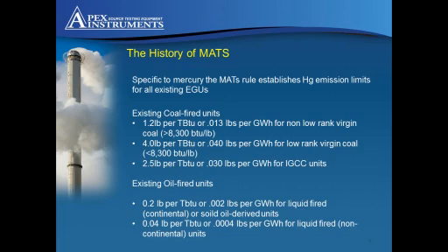It is still unclear if, by reporting emissions against one of these values, you are then locked in to that reporting specification or you can change at will. We are yet to get a determination from the EPA on this particular question. Again, I would like to reiterate that these values on the screen currently are limits for existing EGUs, defined as anything built or reconstructed before the 3rd of May 2011. These limits also apply to those facilities that are based within the lower 48 states.